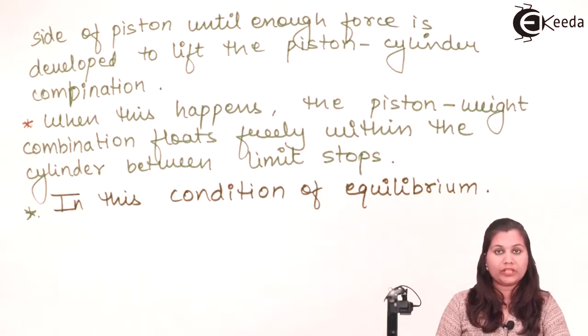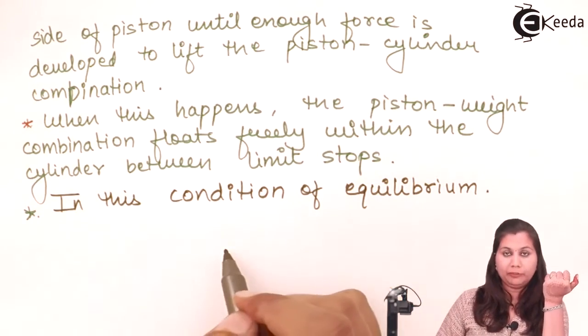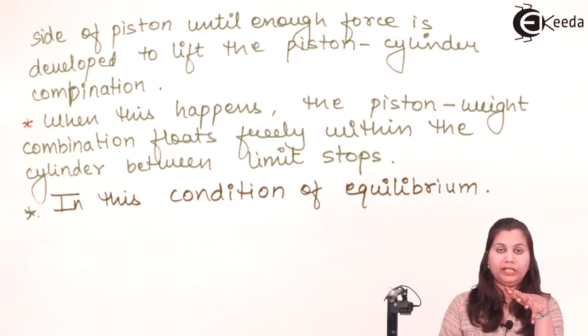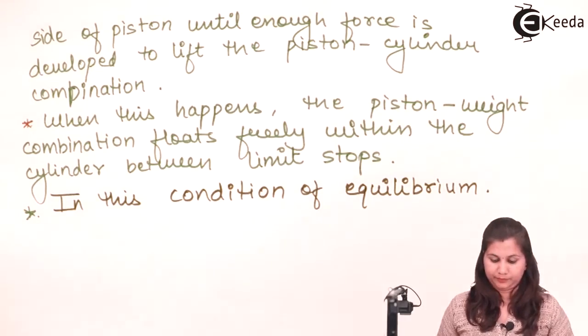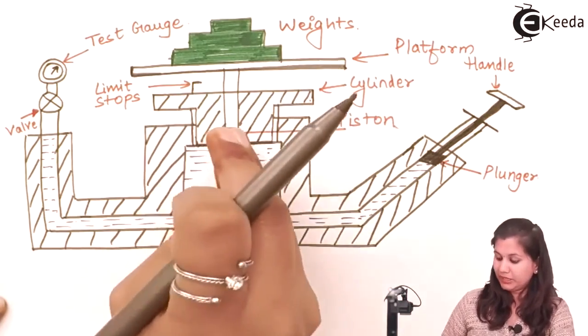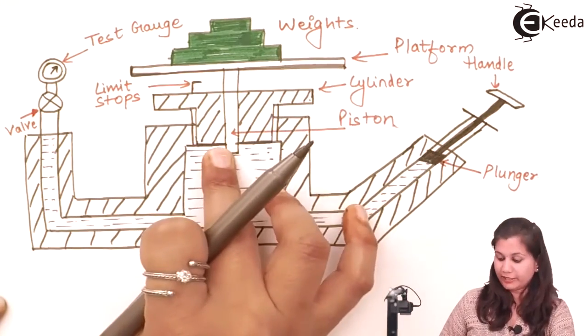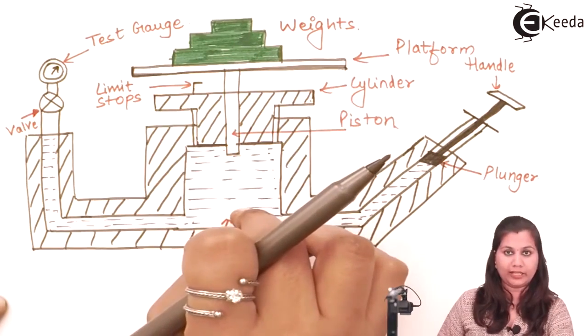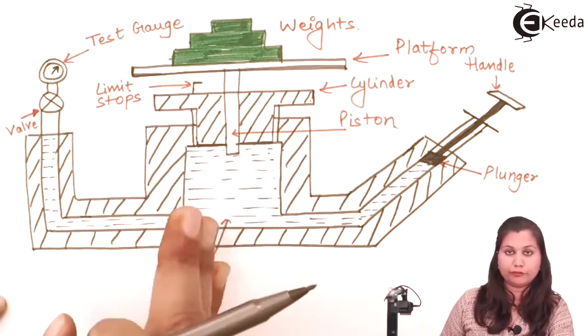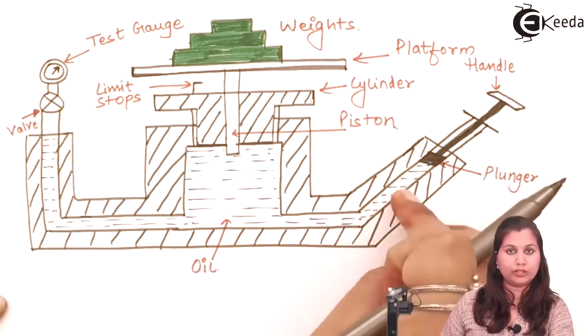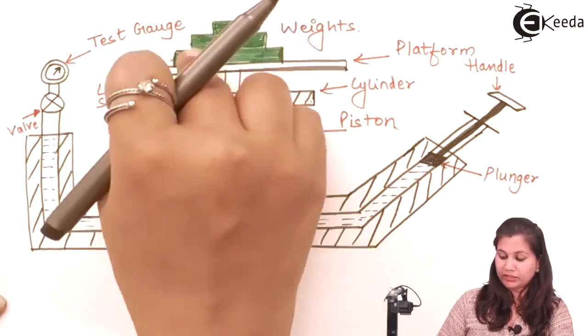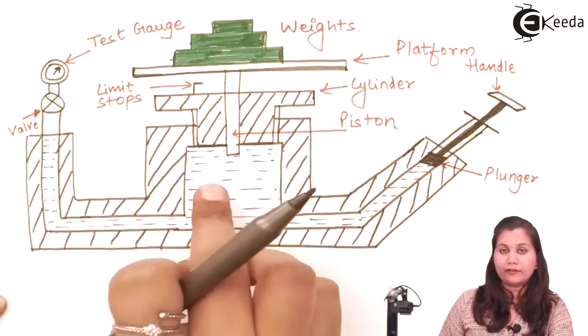So when the piston weight combination is floating freely above the cylinder, in this condition of equilibrium, the pressure of the fluid is equal to the gravitational force of the weight. So when this piston and weight combination is floating freely, it means that the pressure which is applied in the upward direction is equal to the pressure applied in the downward direction. Now in the upward direction, we are having the fluid pressure, which is applied through this plunger, and in the downward direction, we are having the gravitational force of the weight plus the friction drag.